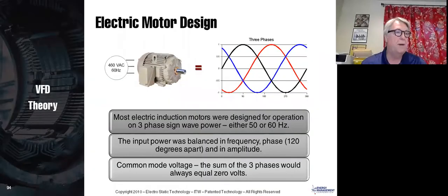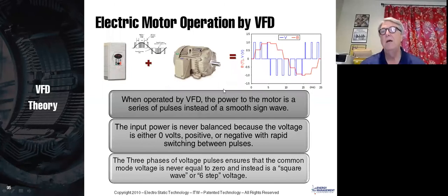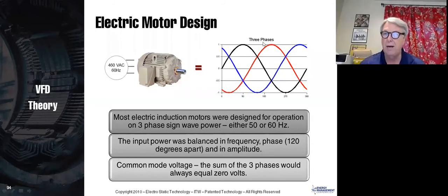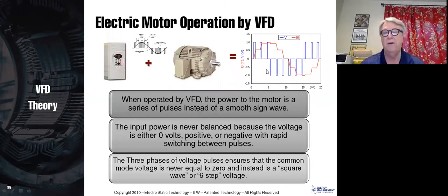Let's talk a little bit about motor bearings. This is the three-phase, and with three-phase, you get very little common mode voltage. Common mode voltage is the voltage between the frame of the motor and the shaft of the motor. When you put it on a VFD, you do not get these added up as you would here, where they add up to 0 at any point in time. On a VFD, they don't. And so you end up with common mode voltages between the frame and the shaft of the motor.